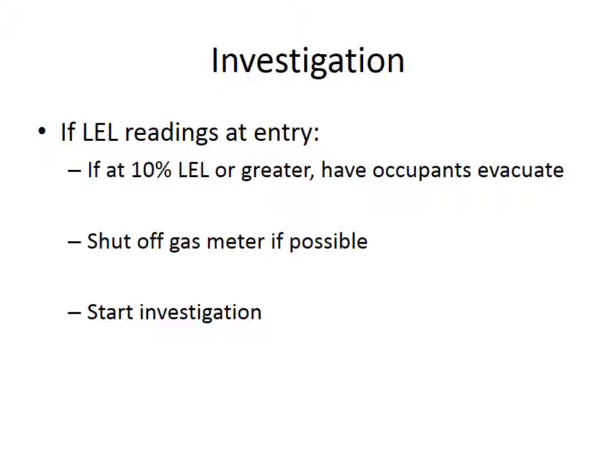Shut off the gas meter if possible. I throw that "if possible" in there because there's situations where we don't want to say absolute. Every time we have a gas leak, we're going to shut the meter off. Think about a complicated commercial building like, for instance, the Highmark Medical Pavilion. Not probably a situation where we pull up, we have a leak in the building, that we're immediately going to shut off their gas, because that could potentially cause more harm to the building.